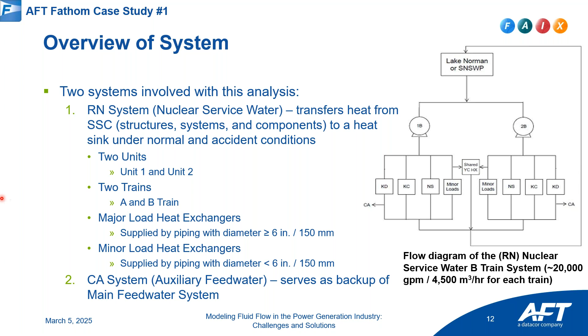Each system that came through on each of the B train systems had flow of about 20,000 GPM, or 4,500 cubic meters an hour, for each of the trains. What had happened over the years, since they were pulling raw water out of this lake, is they would open up the piping that came in on the cooling water system itself, and this is what it would look like inside. There was significant scaling that increased the roughness of the piping, but you can see on the right here how it literally decreased the diameter of the piping, just from the raw water flow. That was buildup and corrosion of the piping.